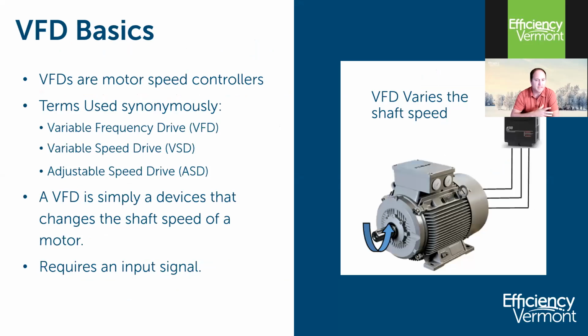So some of the basics, as I mentioned earlier, a VFD is simply a motor speed controller. Absent a drive, a motor can only run at one speed, which is 60 hertz. It loads and unloads based on the demand on the motor. If it's a fan in a fixed volume system, it's going to have a constant load on it. Same goes for a pump. But the point is, absent a drive, it can only run at 60 hertz. And with the drive, it can modulate lower than 60 hertz, and in some cases, it can modulate higher as well.